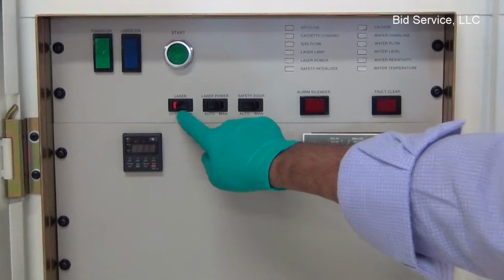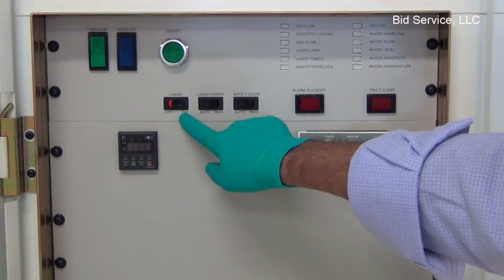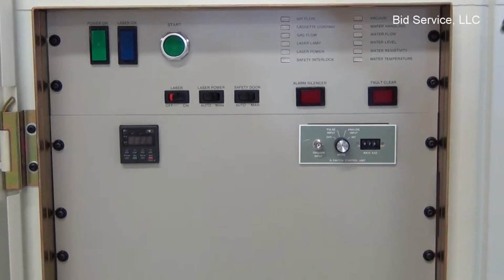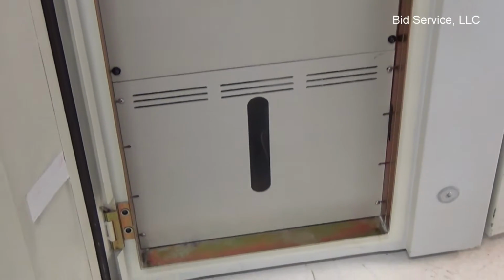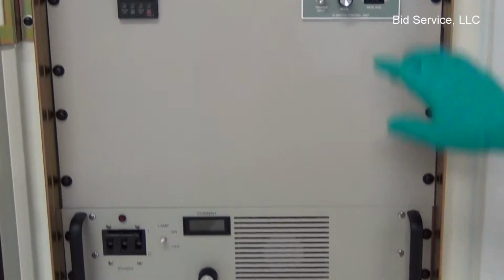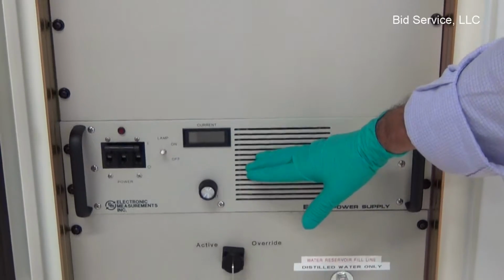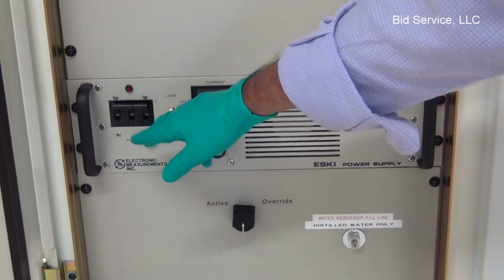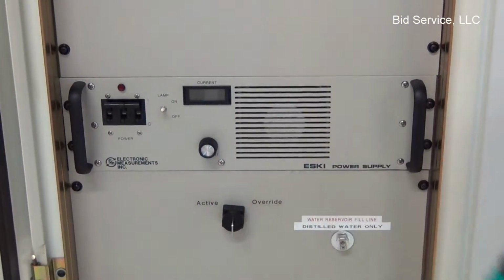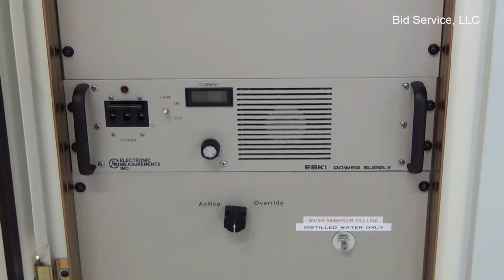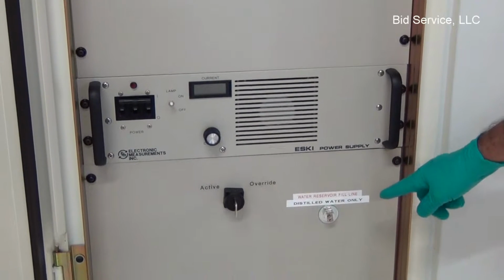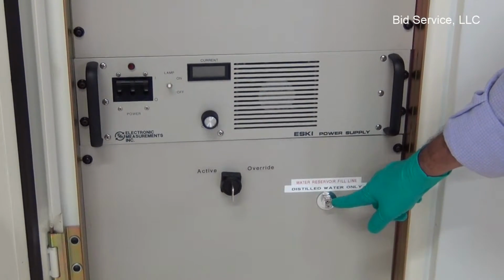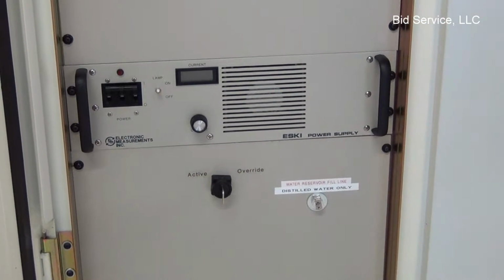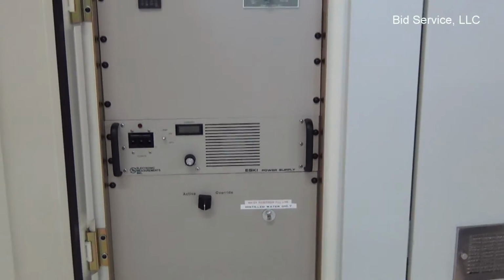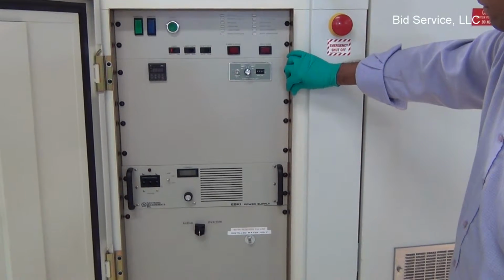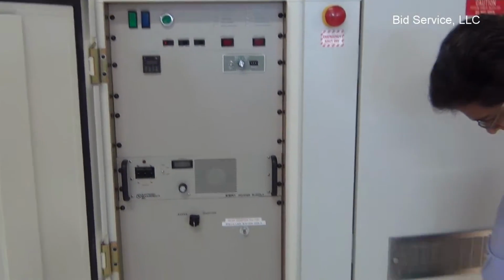And as soon as we turn on the laser, it will turn on the water circulation system, which is at the bottom of the cabinet here. And this is the Q switch control unit for the laser. And the power supply here is for the krypton lamp. And the power supply control main circuit breaker is over here, and in manual mode we can adjust the current from this knob. And the DI water that is circulating in the laser head module can be refilled from this port. This whole cabinet is air circulated by using a blower fan at the bottom here.